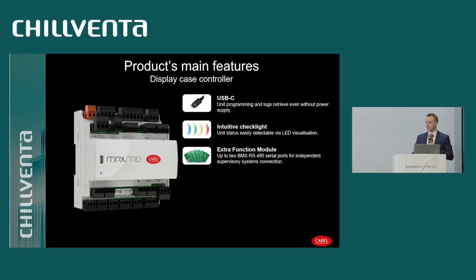The first one is the possibility to include a second BMS port that can be configured as BMS or fieldbus, even with the opto-insulated version. This allows the possibility to connect directly to the controller through 2 different supervisor systems. That could be the refrigeration system and could be another PLC or the building automation system.